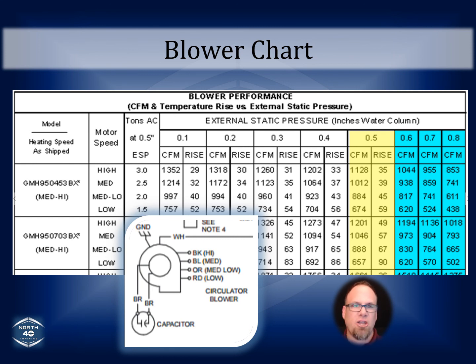So if you're not dehumidifying properly, because it's not charged properly and the airflow is not set properly, that sticks out. And then you run into a situation where maybe you have some cool air, but it's cool and it's clammy, so it's a little moist. It's not dehumidifying. You run into kind of a funky smell as well.